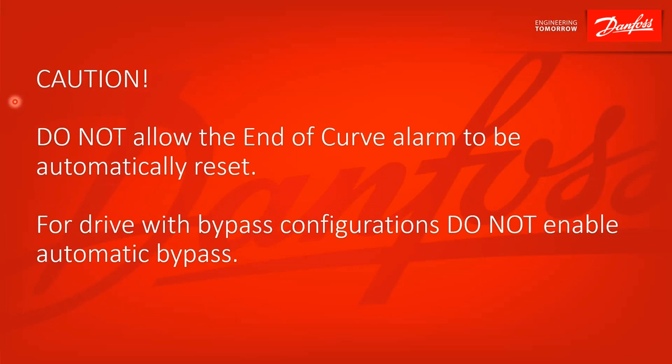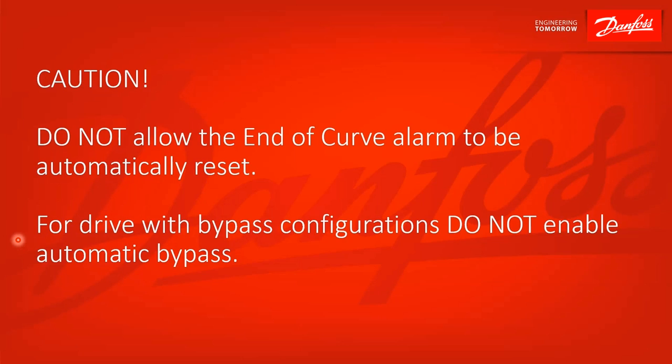These are two very important cautions. Do not let the end of curve alarm be automatically reset. Otherwise, you would just keep running into that broken pipe or that leak situation. And for drives with bypass configurations, do not enable automatic bypass. That would cause the motor to be run directly off the line in that condition, and that would not be good.